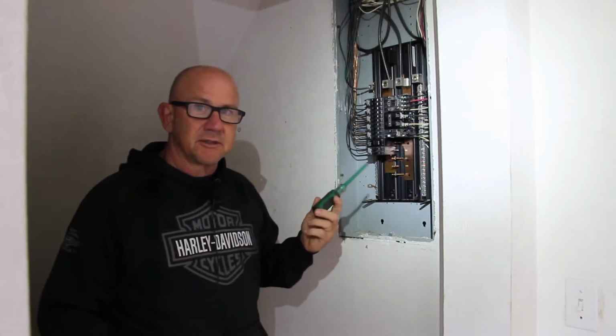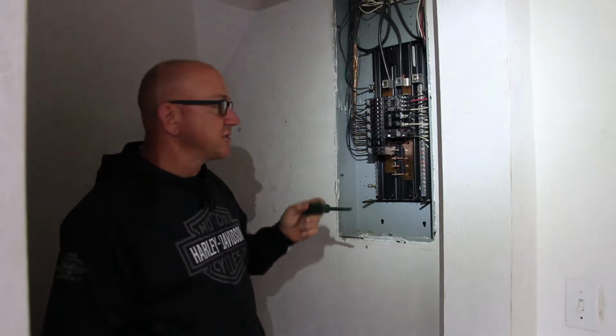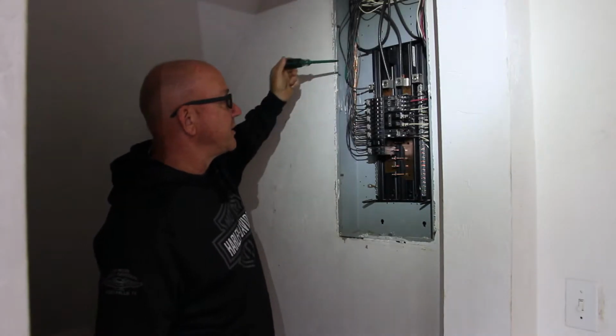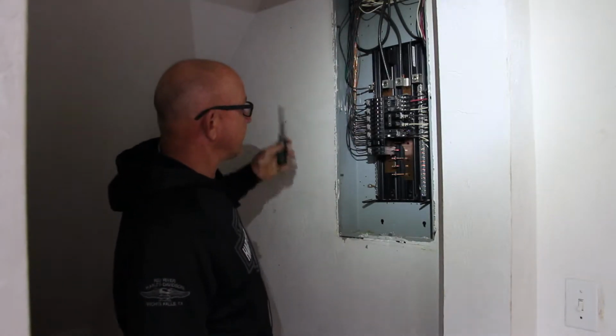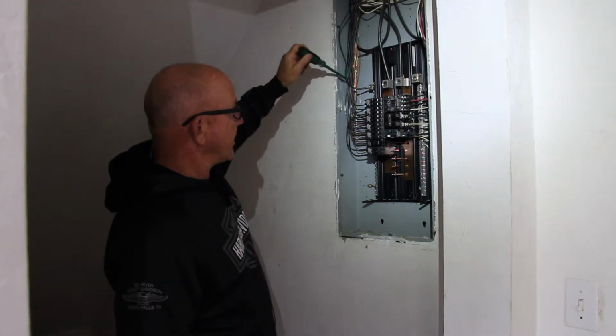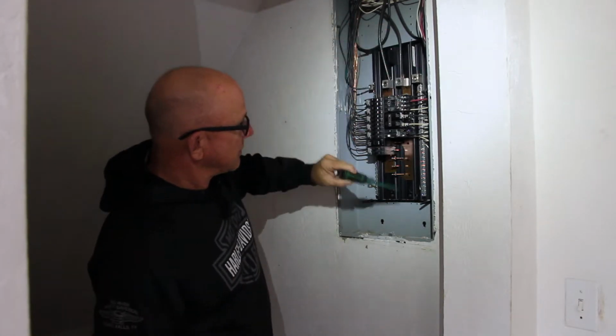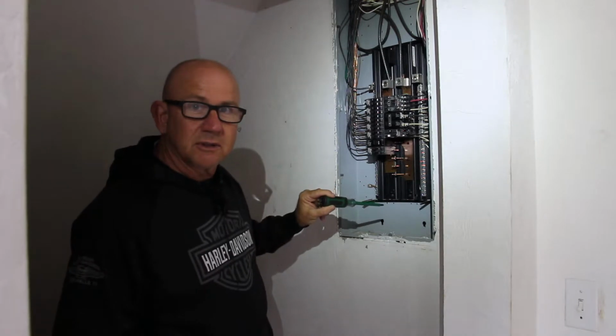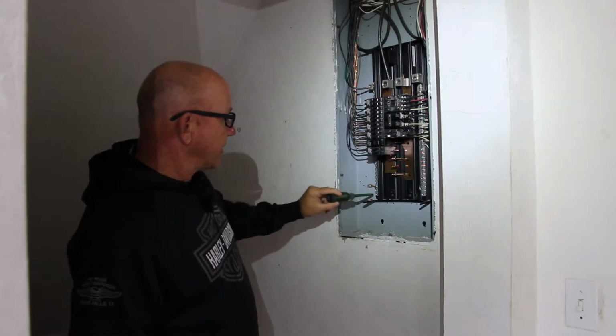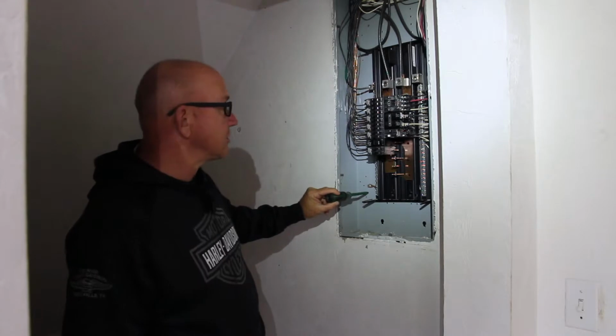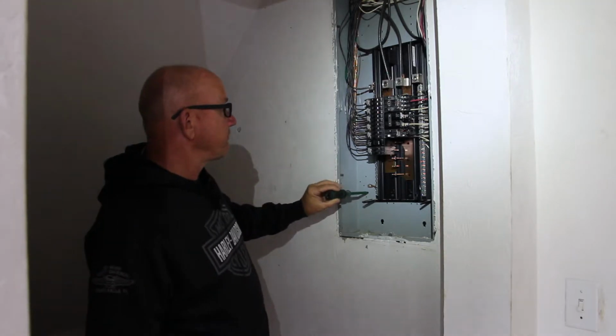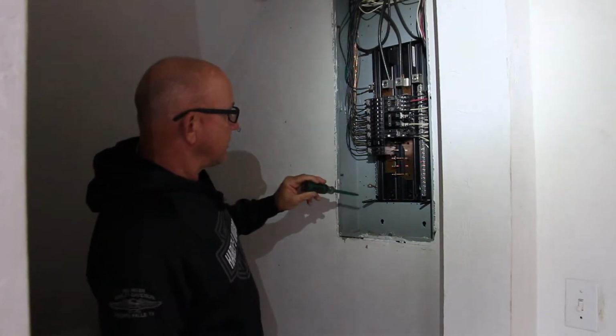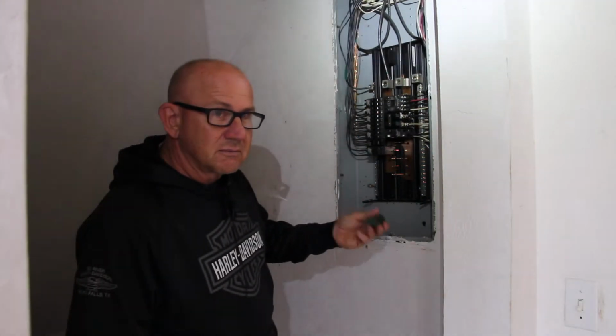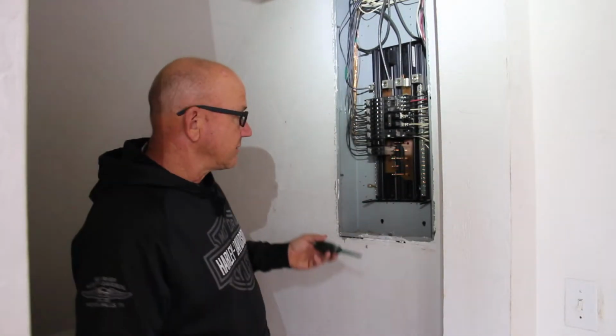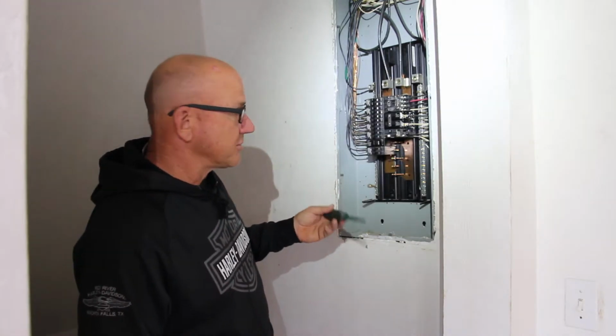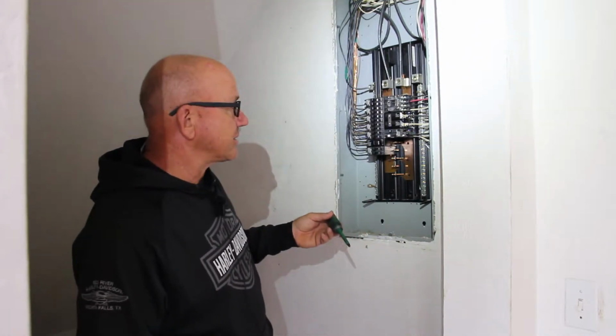One of the major problems here is this must have a service disconnect at the panel where these 2 feeders come in. We're also going to identify that the grounding bar and the neutral bar are separated, which is the way that it's supposed to be. The grounding bar is bonded to the electrical panel, which is the way that it is supposed to be. Those are a couple of good things, and it's sometimes a good idea to mention that when your customers are with you during the inspection.